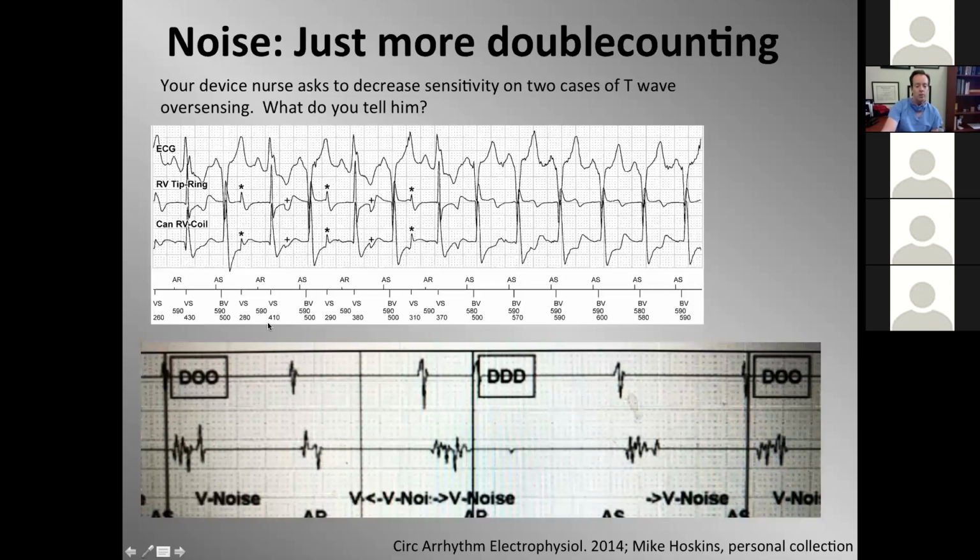So we see cyclical noise. We see QRS noise, QRS noise, QRS noise that roughly corresponds with the T wave. The problem is that it's intermittent and high frequency. Here we see A pace, V sense with some weird high frequency noise right after each V sense event.